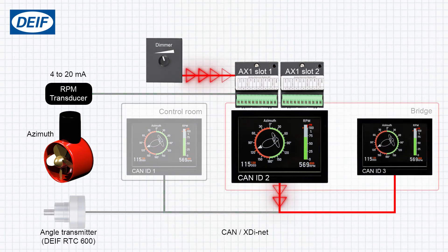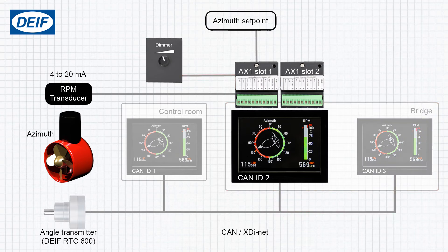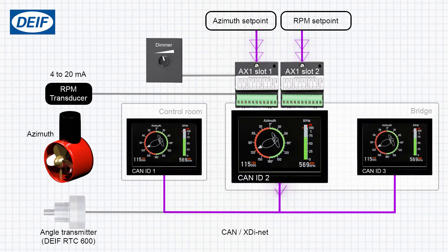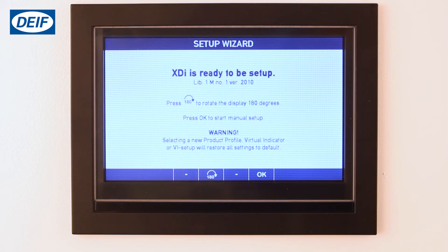A dimmer is also connected to the first analog module, and the value is transmitted over XDInet to all the XDIs in the same dimmer group. The azimuth setpoint value is connected to the first analog module and the RPM setpoint to the second analog module. Both of these are also transmitted over XDInet to all the XDIs.